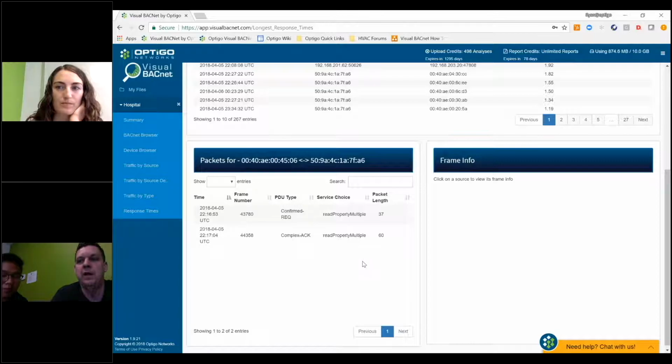Now, for those of you that don't know, we can actually use this trick. You can always set a read request between any network or segment from controller to controller. So if your customer is complaining of slow graphics from a specific system, put a read request on it. Let's time it, because we'll time it automatically and you can see what the issue is.